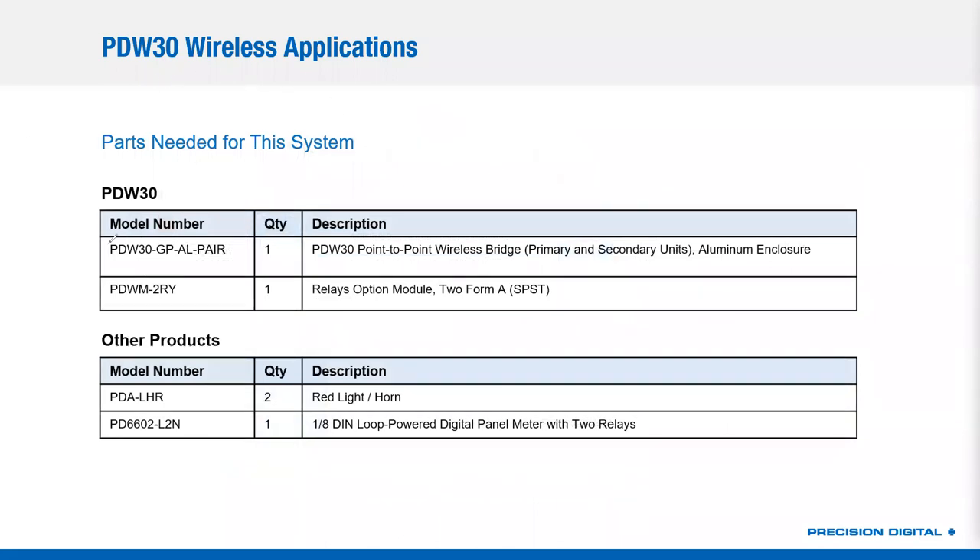Now let's talk about what you need to actually build that system. We start by ordering a pair of PDW-30s for general purpose area in aluminum — one of those, which comes with both the primary and secondary units. That's a key concept with the PDW-30s: you get both units of the pair when you buy one. Then I want two 5-amp relays to run my lights and horns, so I get one PDWM-2RY relay module, just for the field mount side by the tank, plus the two lights and horns and the loop-powered meter. In total, five items ordered for a complete wireless system.